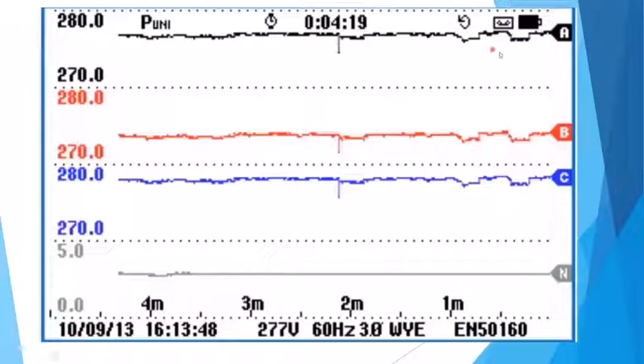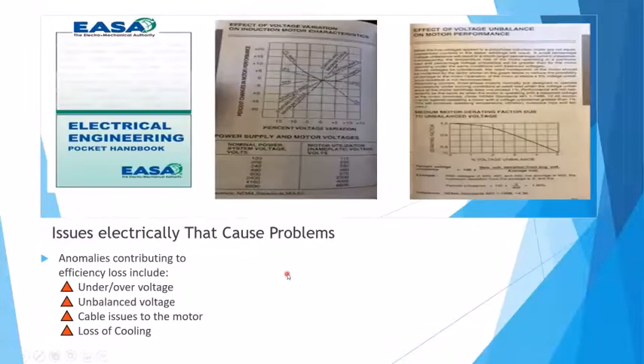Again, the meter can show you back here some of the peaking power, spikes, jags. So you can actually get it down to a point of what did cause that power. It's connectable to either a Y source or a delta source. And it's important that when you do set them up, you set that up. And that means, what is the transformer providing for power into the unit?